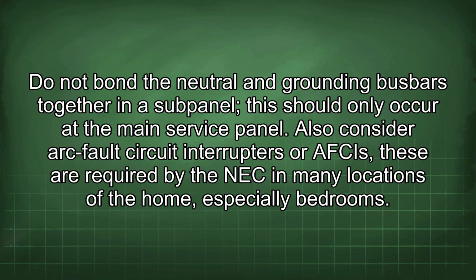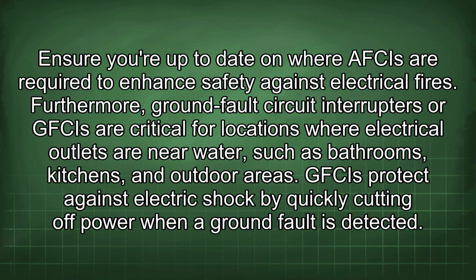Also consider arc fault circuit interrupters, or AFCIs. These are required by the NEC in many locations of the home, especially bedrooms. Ensure you are up to date on where AFCIs are required to enhance safety against electrical fires. Furthermore, ground fault circuit interrupters, or GFCIs, are critical for locations where electrical outlets are near water, such as bathrooms, kitchens, and outdoor areas. GFCIs protect against electric shock by quickly cutting off power when a ground fault is detected.